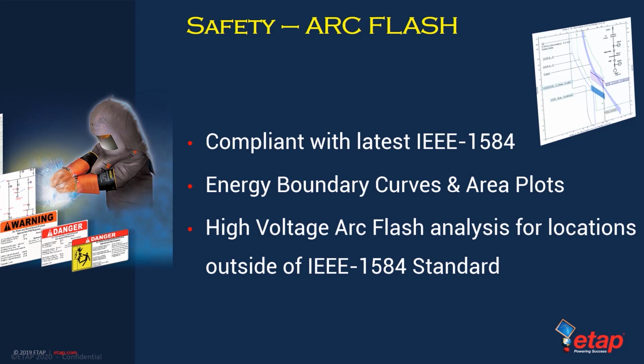Moving on to safety and arc flash. Full compliance with the latest IEEE 1584 standard and solutions such as energy boundary area plots, which is a unique probabilistic approach tool for calculating incident energy safety range that takes into account tolerances in enclosure area or volume and electrode configuration. This is extremely useful on IEEE 1584 2018 standard, since we are now responsible for collecting enclosure area and electrode configuration. Very useful for design engineers during a front-end engineering design project when enclosure dimensions and electrode orientation may not be available.